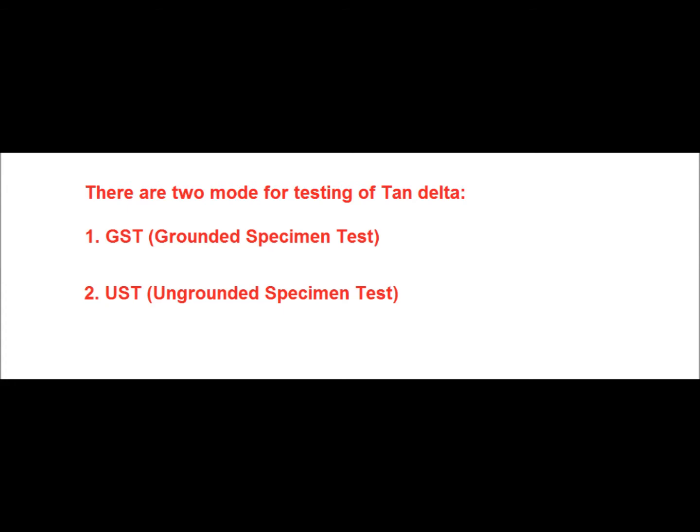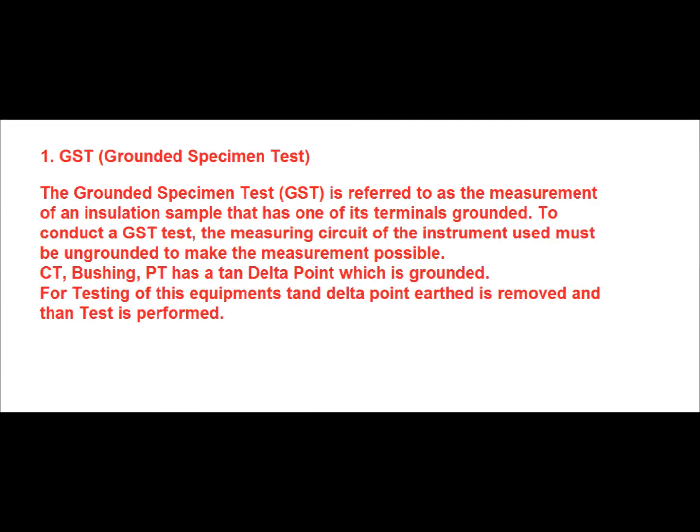In GST — grounded specimen test — the test is referred to as the measurement of an insulation sample that has one of its terminals grounded or earthed. To conduct a test in GST mode, the measuring circuit of the instrument used must be ungrounded to make the measurement possible.